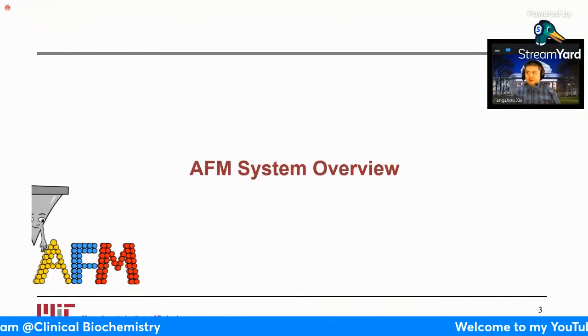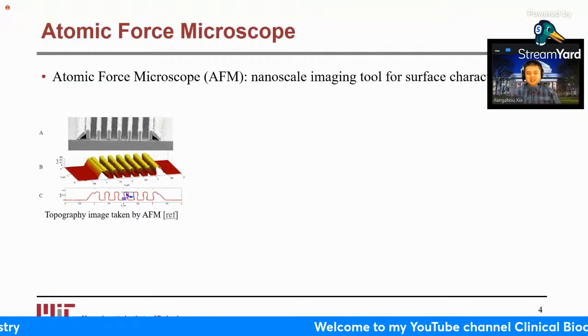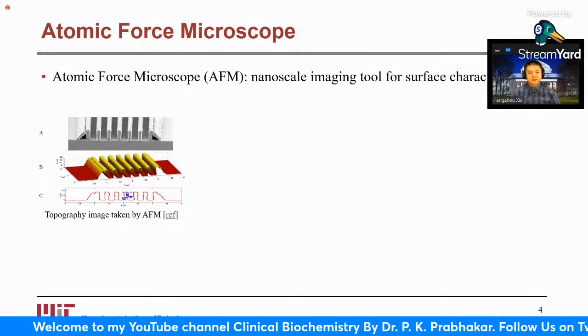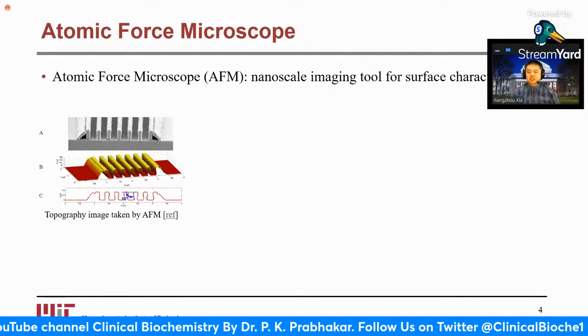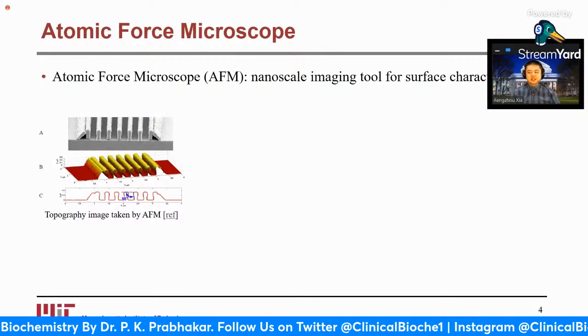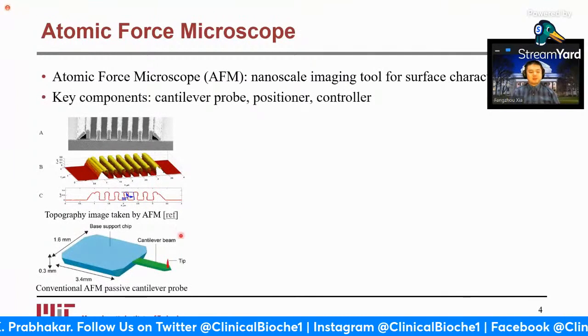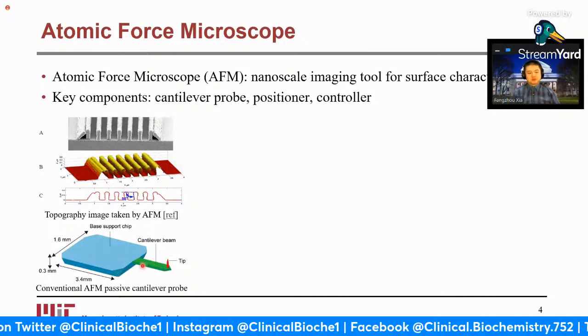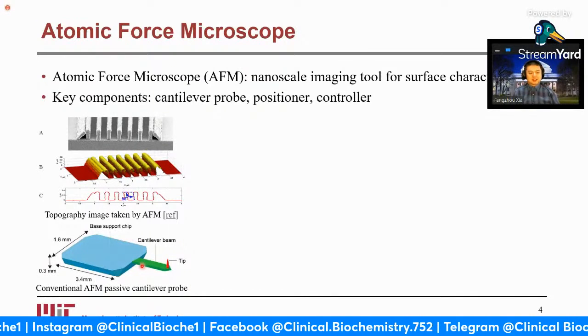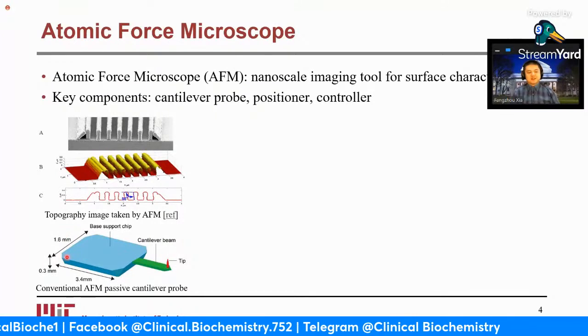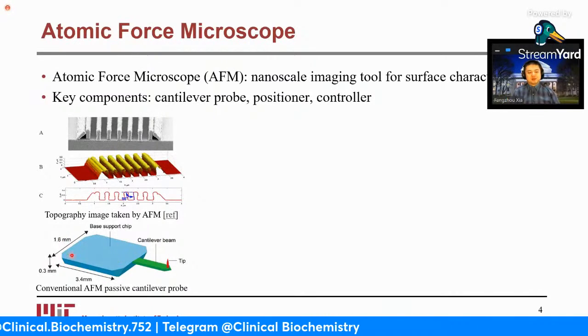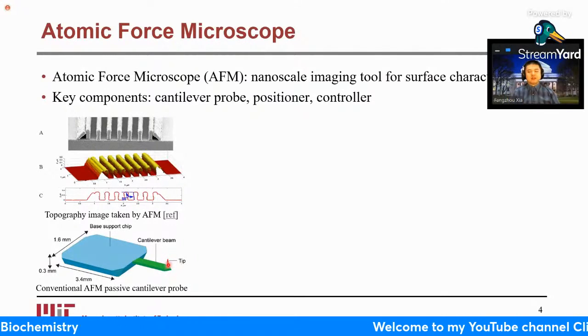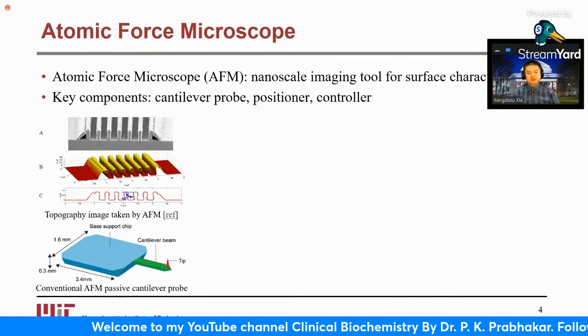As an overview, we particularly start AFM with surface characterization, including topography, as it's a very basic modality. For imaging at this nanoscale resolution, we need three key subcomponents in the AFM system. The first is the cantilever probe, a passive one here; we'll talk about what is passive and what is active in the next slide. This probe is a very typical one people use in research. We have the support chip where we keep the tweezers on, and then the actual cantilever with a sharp tip at the end of it.